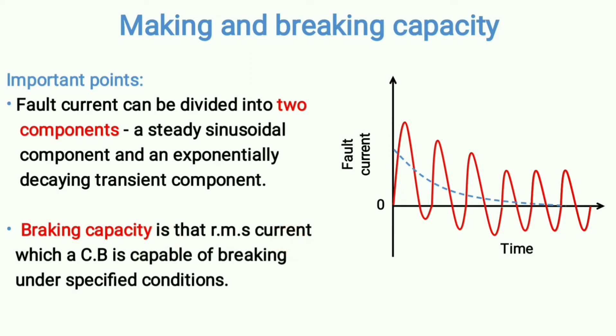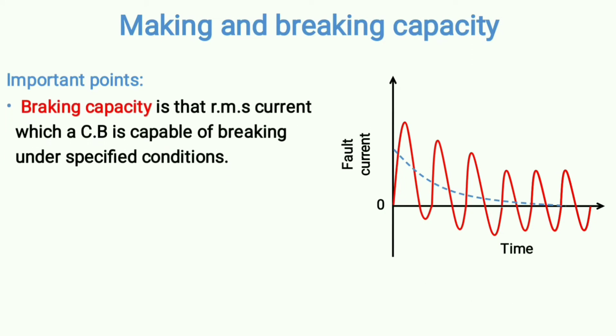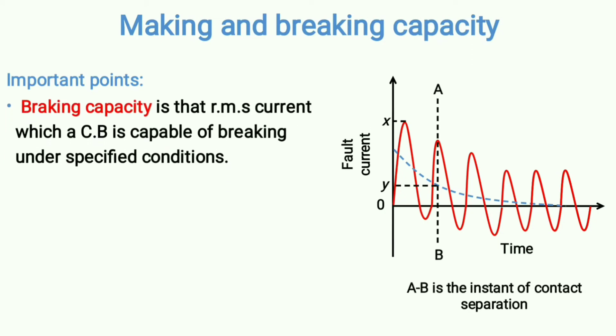Breaking capacity is the RMS current which a circuit breaker is capable of breaking under specified conditions. Whenever a fault happens, the circuit breaker has to disconnect the path. Breaking capacity shows the RMS value of the fault current which the circuit breaker is capable of breaking under specified conditions — at a particular recovery voltage or a particular striking voltage.